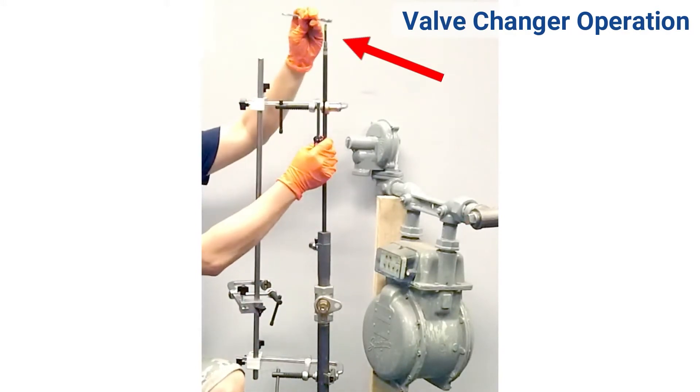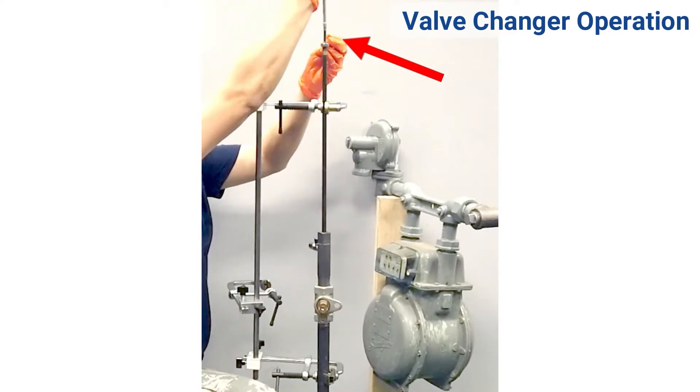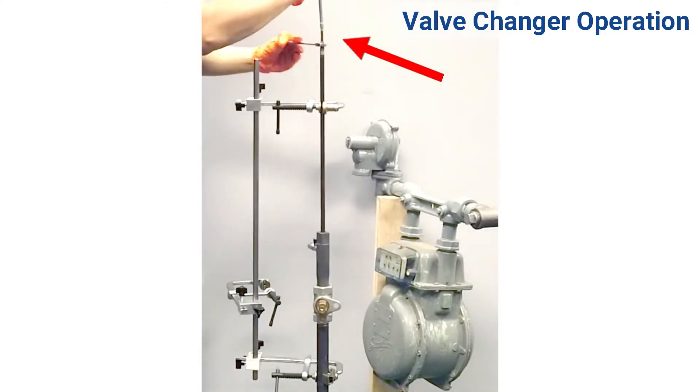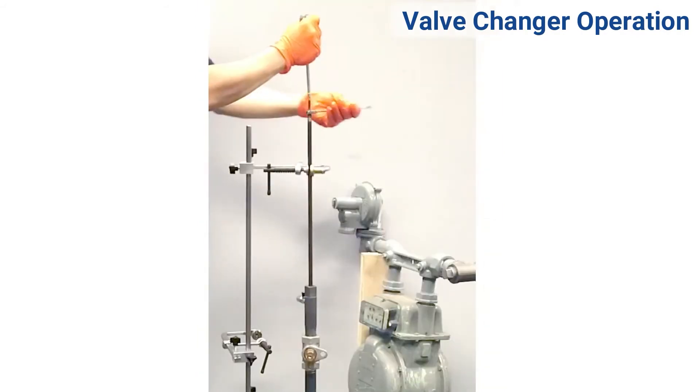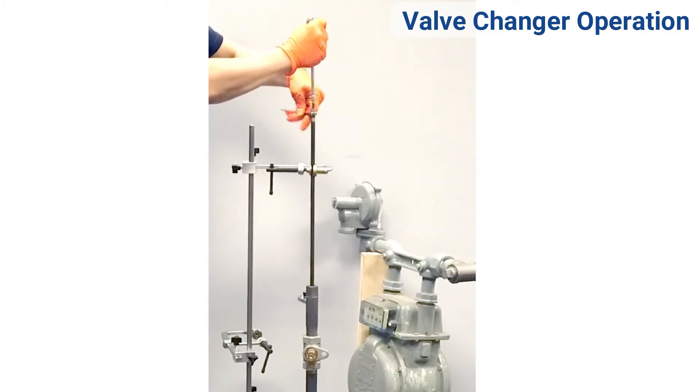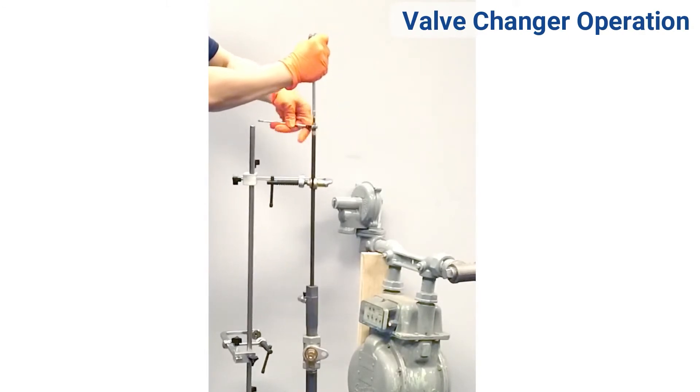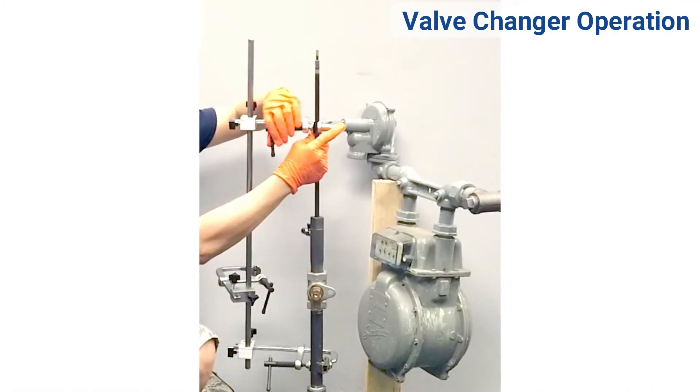Once the meter valve has been tightened, loosen the rubber stopper until less than three quarters of an inch of threads are showing at the top of the shaft. This means the rubber stopper is fully relaxed. Loosen the top clamp and swing out of the way.